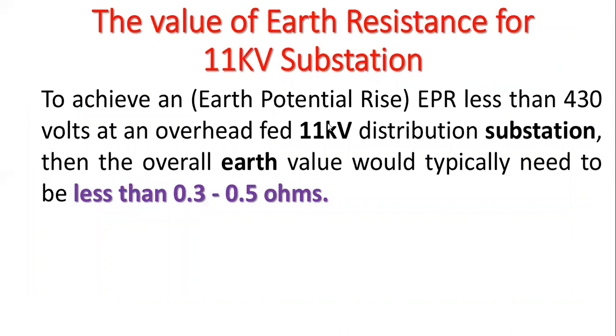Then next, the value of the earth resistance for 11 kV substation. To achieve an earth potential rise, the EPR, which is less than 430 volt at an overhead 11 kV distribution substation, that means pole mounted substation or plinth mounted substation, the overall earth value typically needs to be less than 0.3 to 0.5 ohm. In some cases it will be more. That means that earthing resistance value you have to reduce by continuously adding water or continuously adding salt. By adding that salt, you can reduce the value of the earth resistance, so that you maintain the value of the earth resistance as low as possible.